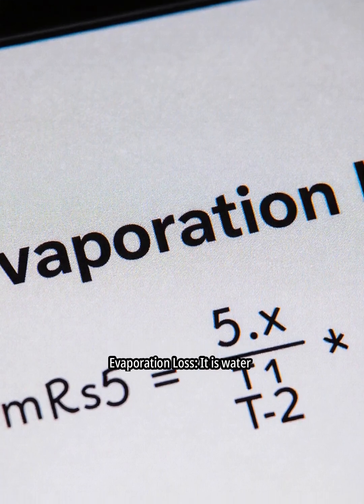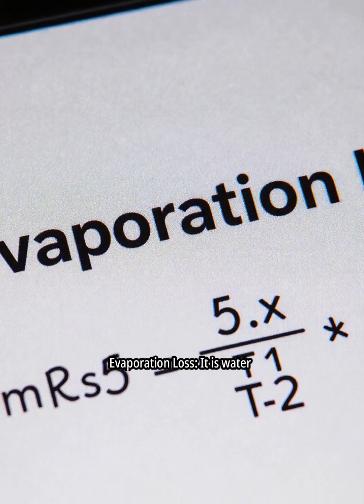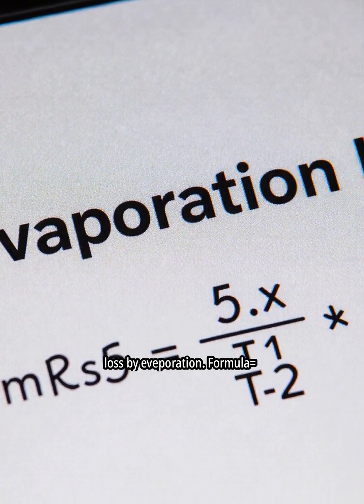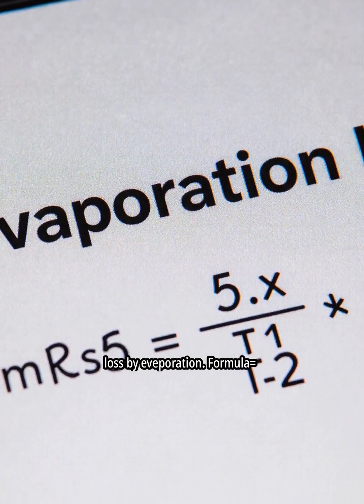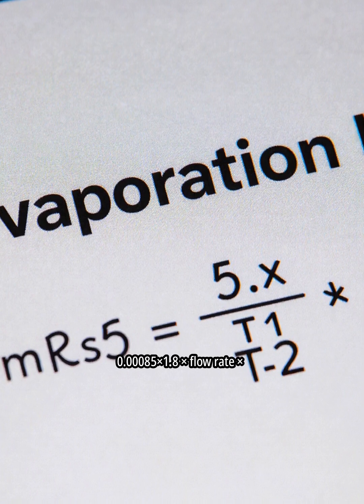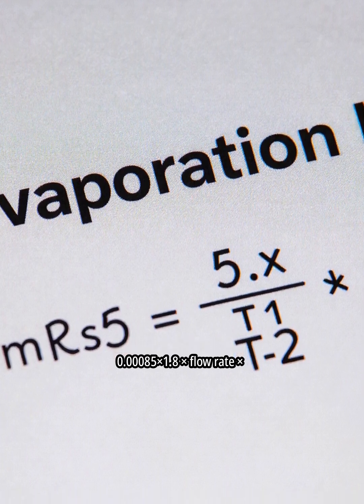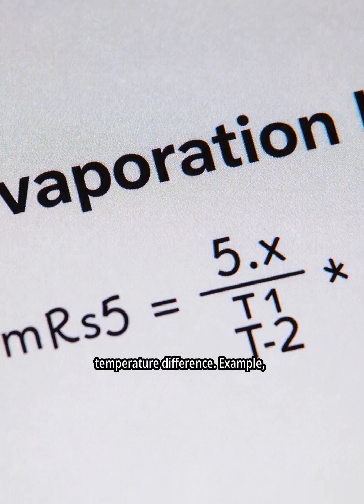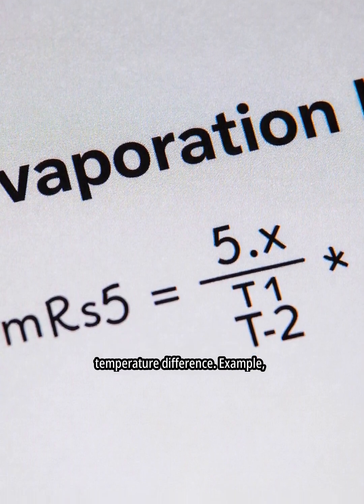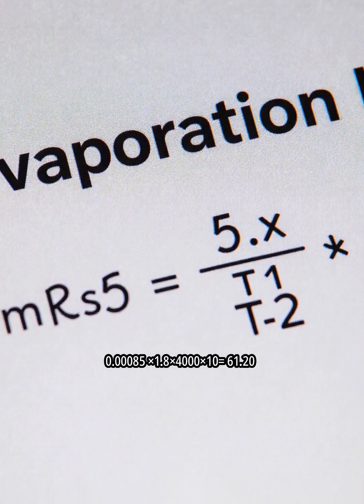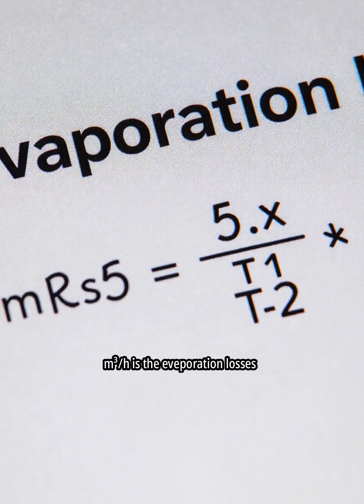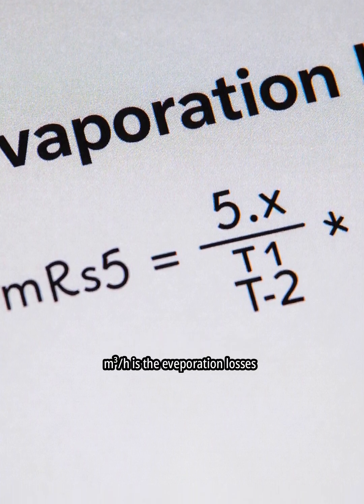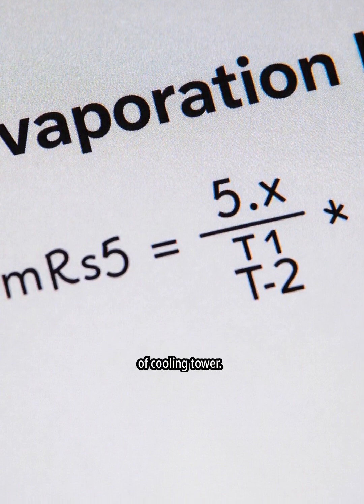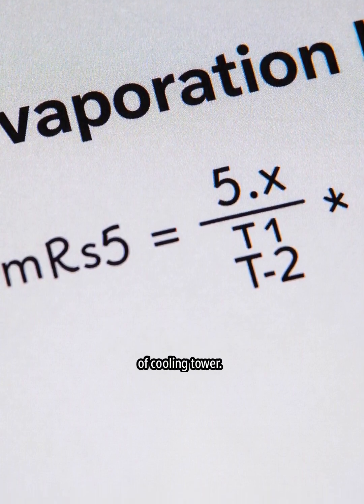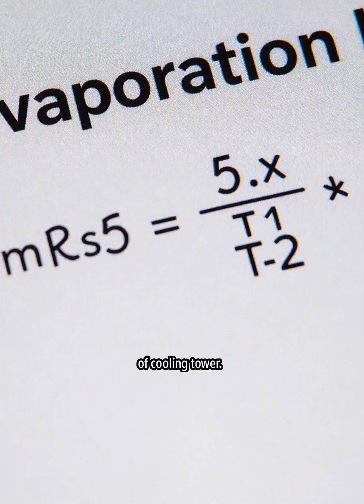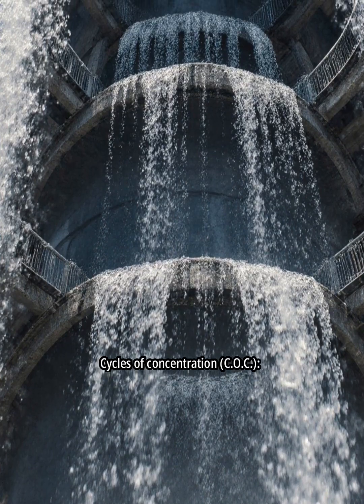Evaporation loss. It is water loss by evaporation. Formula equals 0.00085 times 1.8 times flow rate times temperature difference. Example, 0.00085 times 1.8 times 4,000 times 10 equals 61.2 cubic meters per hour is the evaporation loss of the cooling tower. Cycles of concentration.